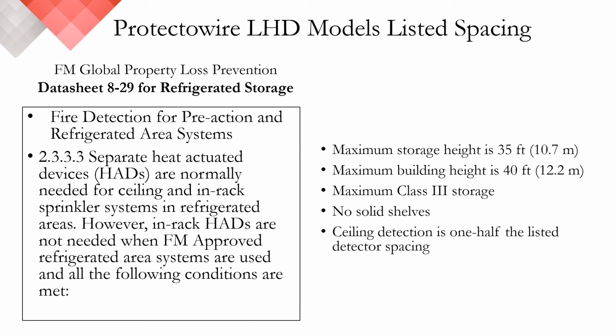There are some additional facility requirements that must be considered if you intend to avoid in-rack detection. The maximum hazard needs to be Class 3, there can be no solid shelves in the racks, and ceiling detection needs to be 1/2 of the listed spacing, but not less than that of the sprinkler spacing.